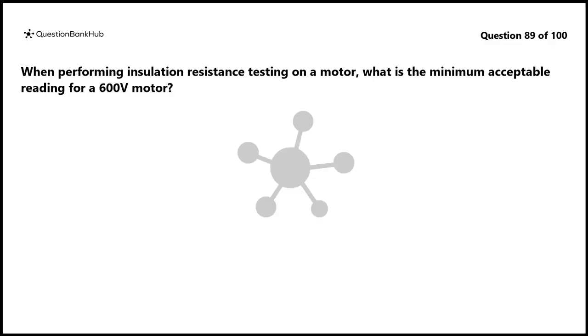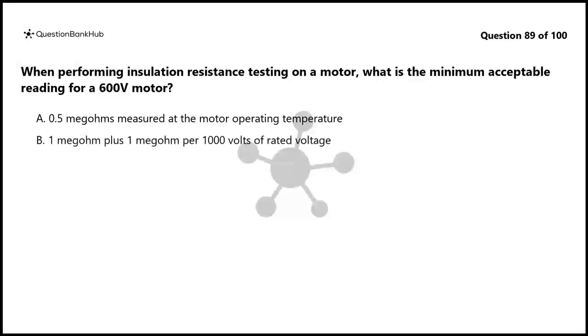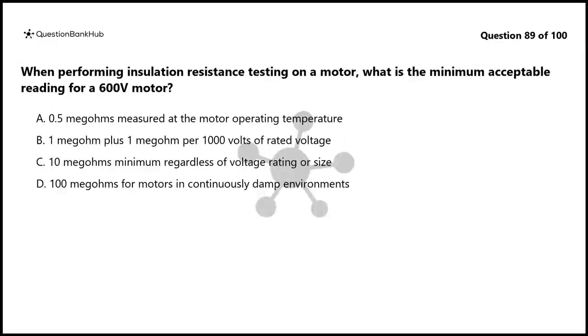Question 89. When performing insulation resistance testing on a motor, what is the minimum acceptable reading for a 600 volt motor? A. 0.5 megohms measured at the motor operating temperature. B. 1 megohm plus 1 megohm per 1000 volts of rated voltage. C. 10 megohms minimum regardless of voltage rating or size. D. 100 megohms for motors in continuously damp environments.